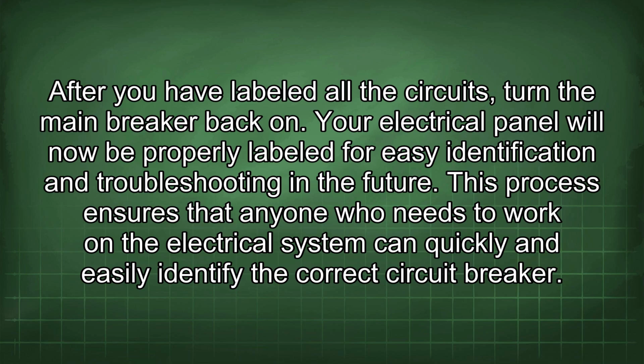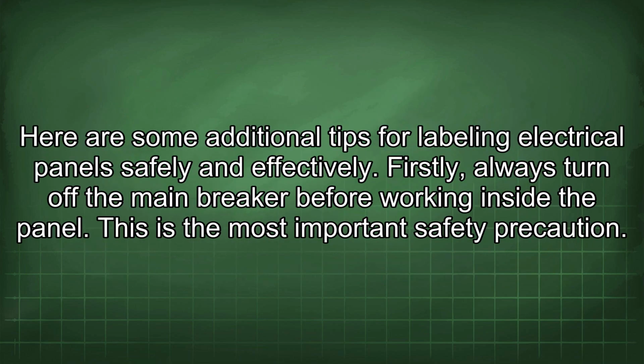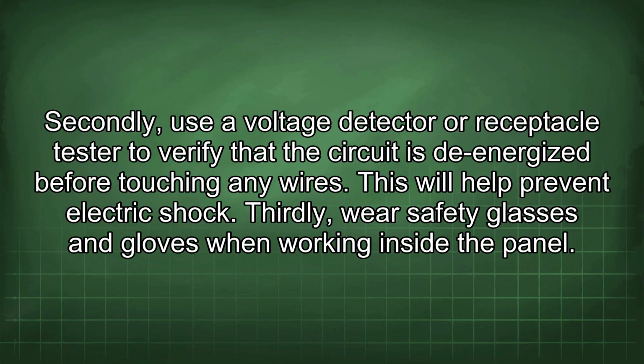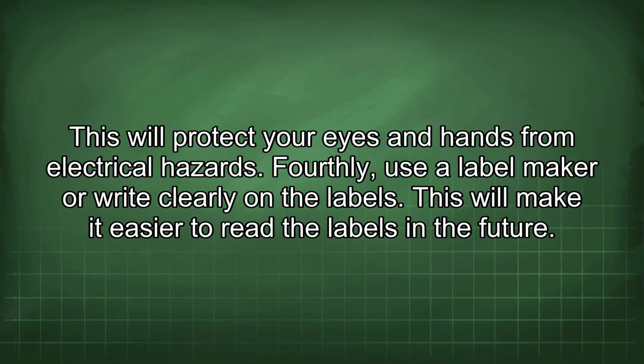circuit breaker. Here are some additional tips for labeling electrical panels safely and effectively. Firstly, always turn off the main breaker before working inside the panel. This is the most important safety precaution. Secondly, use a voltage detector or receptacle tester to verify that the circuit is de-energized before touching any wires. This will help prevent electric shock. Thirdly, wear safety glasses and gloves when working inside the panel. This will protect your eyes and hands from electrical hazards.